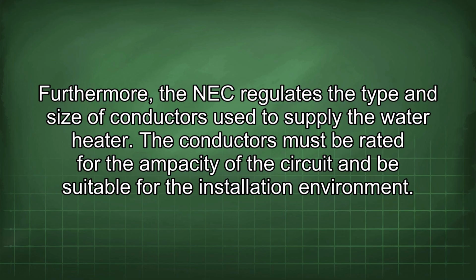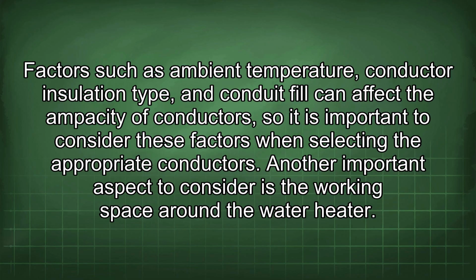Furthermore, the NEC regulates the type and size of conductors used to supply the water heater. The conductors must be rated for the ampacity of the circuit and be suitable for the installation environment. Factors such as ambient temperature, conductor insulation type, and conduit fill can affect the ampacity of conductors, so it is important to consider these factors when selecting the appropriate conductors.